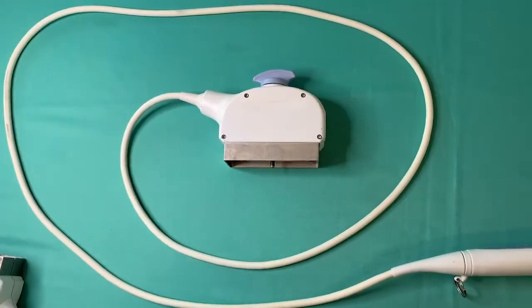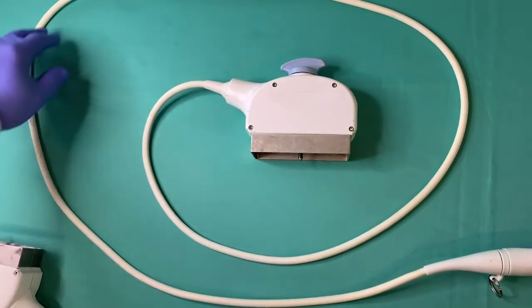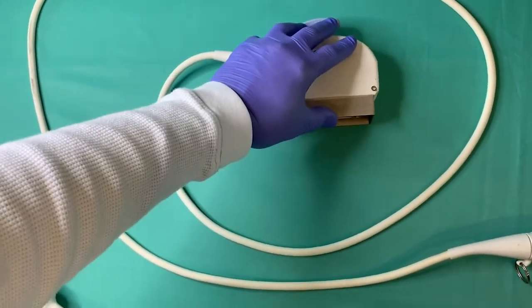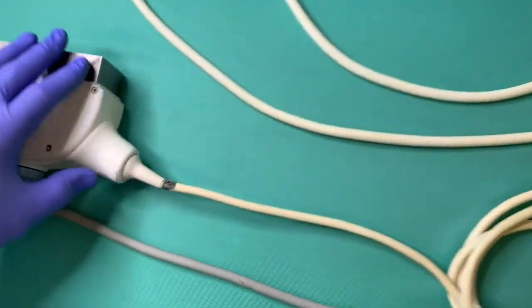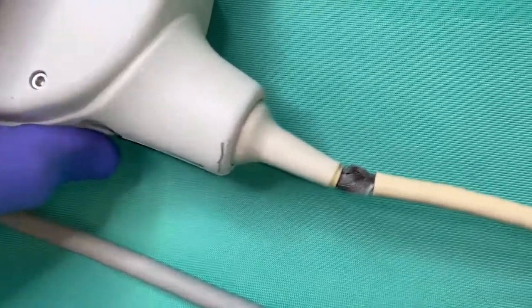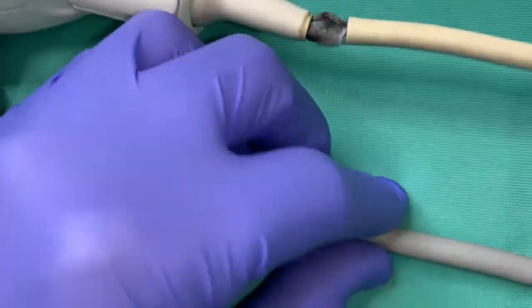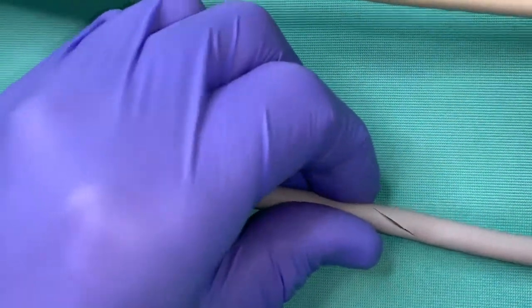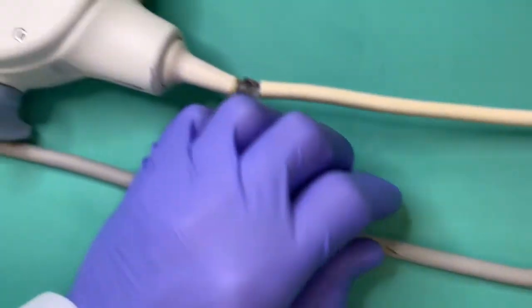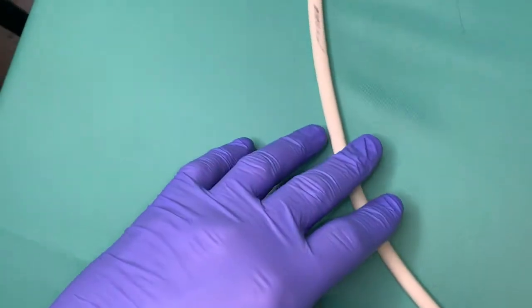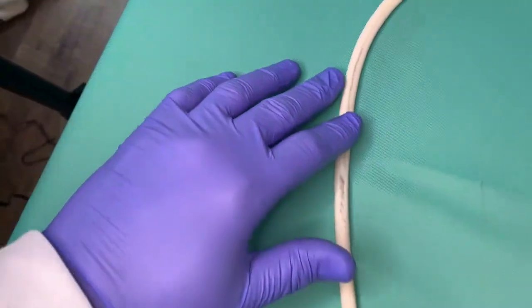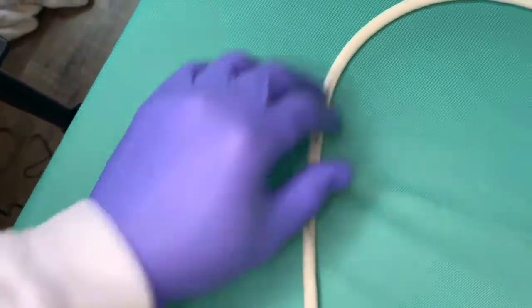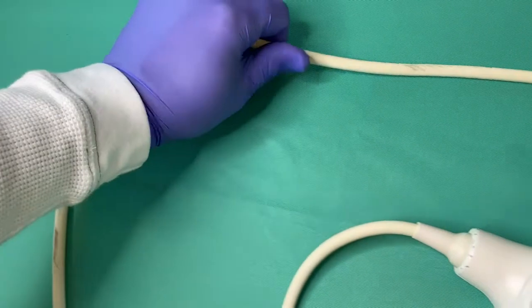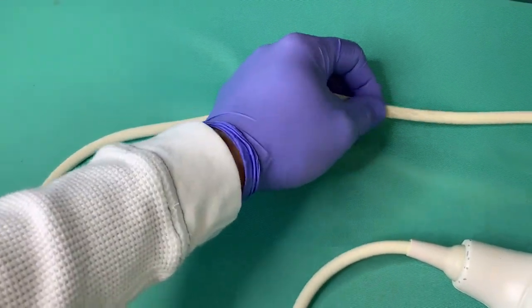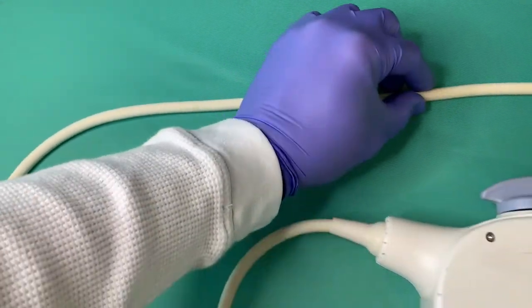The system cable spans the distance between the system connector and the scan head. The cable should not possess any cuts, tears, or deep abrasions. The cable may appear slightly scuffed, slightly stained, or even marked. It's a good idea to run your hand along the entire length of the cable, feeling for abnormalities such as flatness, rollover damage, or kinks, which could indicate some internal damage.